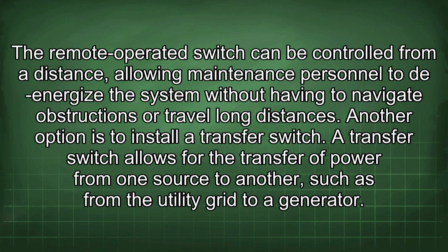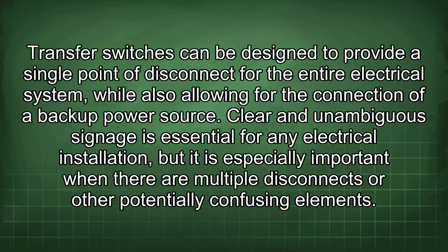Another option is to install a transfer switch. A transfer switch allows for the transfer of power from one source to another, such as from the utility grid to a generator. Transfer switches can be designed to provide a single point of disconnect for the entire electrical system, while also allowing for the connection of a backup power source.